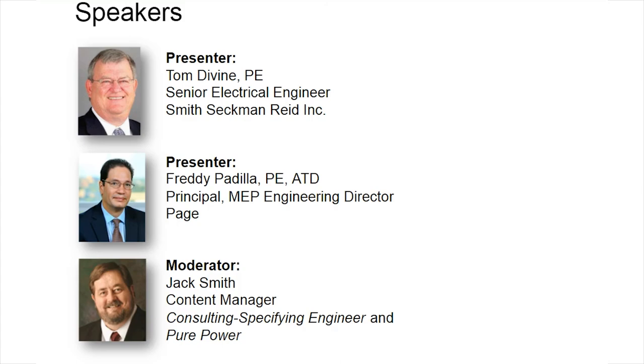Okay, basically, both of them serve the same purpose, it's just to ensure that the load does not lose power at any time. So it's a big difference between the two. Usually it's in the amount of time that this system gets implemented. A UPS usually uses batteries, and the batteries these days can last from 1 minute to 2 hours, 3 hours, as many as you can put in.